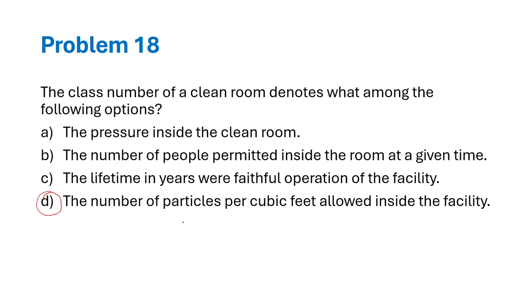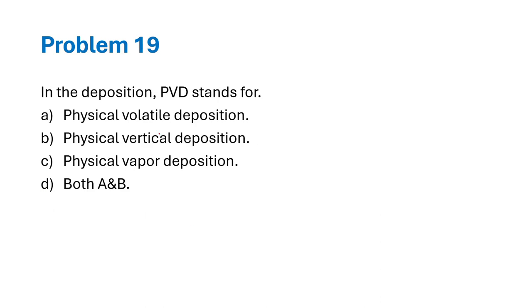So there are various classes, class 100, 1000, 10,000 and so on. Class 100 will have very few particles per cubic feet. In a clean room, the lithography process is very critical, and the room should not have many particles, so that area will have the lowest class in a clean room in general.